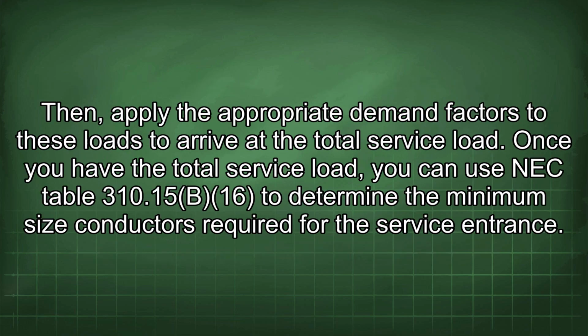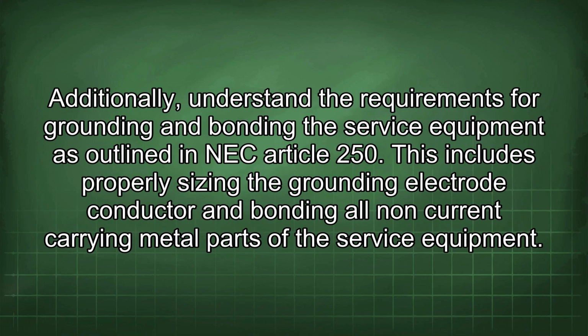Then apply the appropriate demand factors to these loads to arrive at the total service load. Once you have the total service load, you can use NEC Table 310.15(B)(16) to determine the minimum size conductors required for the service entrance. Additionally, understand the requirements for grounding and bonding the service equipment as outlined in NEC Article 250. This includes properly sizing the grounding electrode conductor and bonding all non-current carrying metal parts of the service equipment.